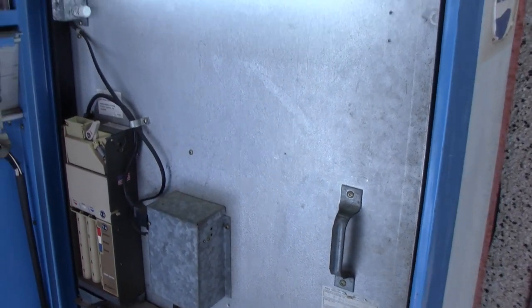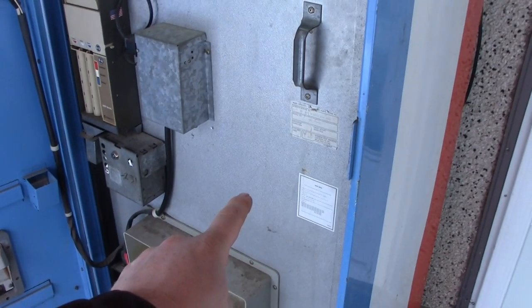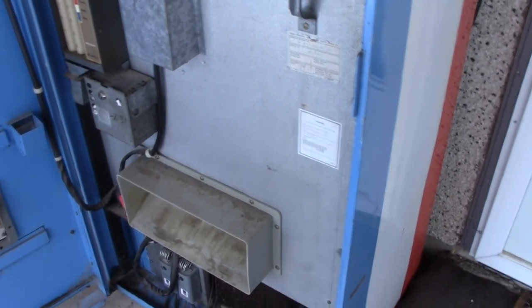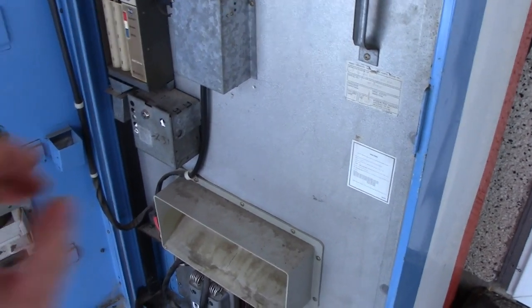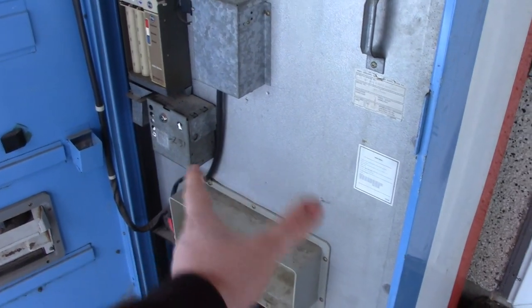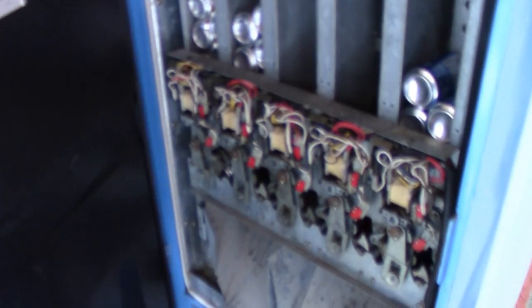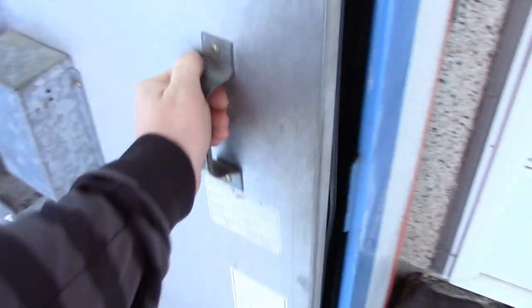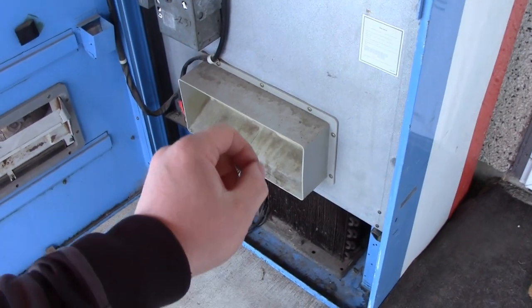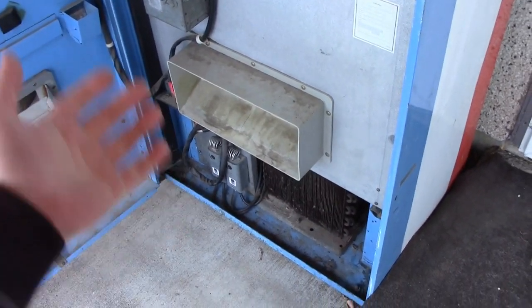Inside the machine, it's just running away happily. I can hear a fan burring away inside, but I don't hear a compressor — because it's so cold that the inside of the box satisfies super easily. It'll turn on in the morning and the compressor won't turn on because it's already like minus two inside the box. That inductive fan in there is a bit of a problem because, being an inductive fan motor, it will always generate heat, and as a result the inside of the box will eventually heat up to a point where the compressor's going to turn on.